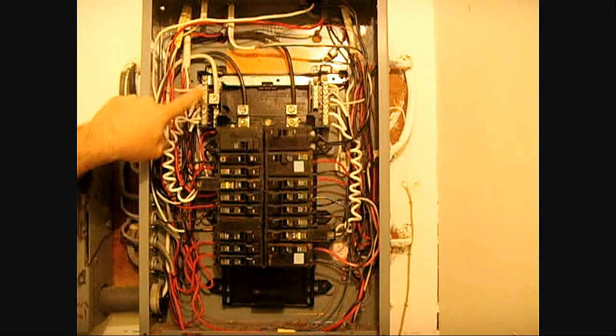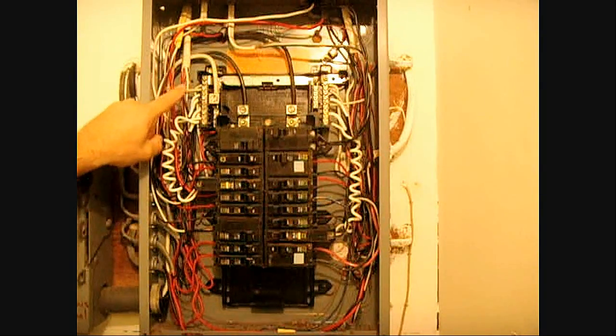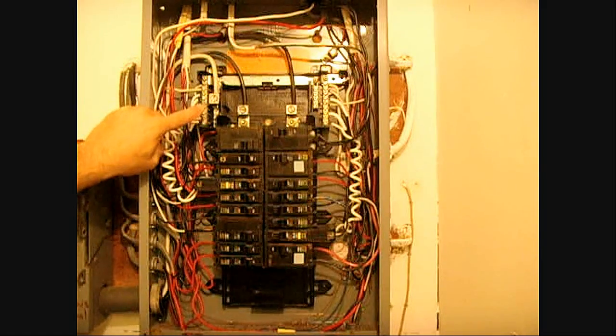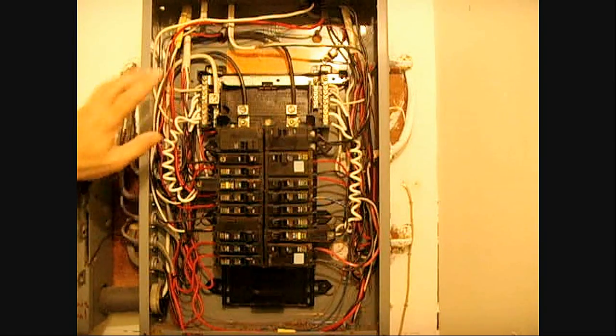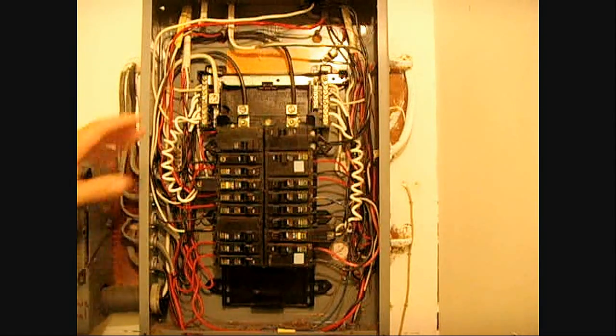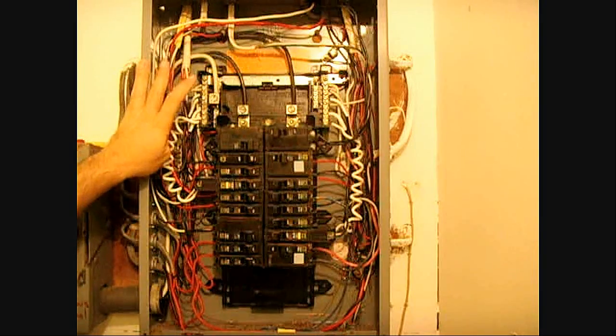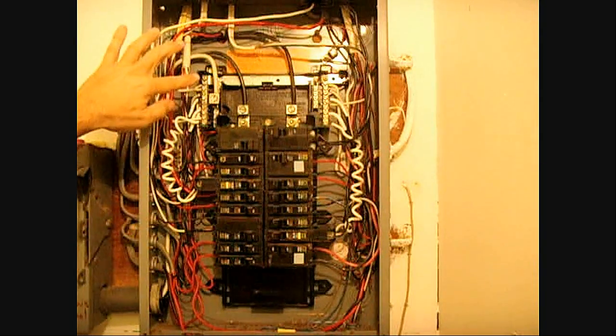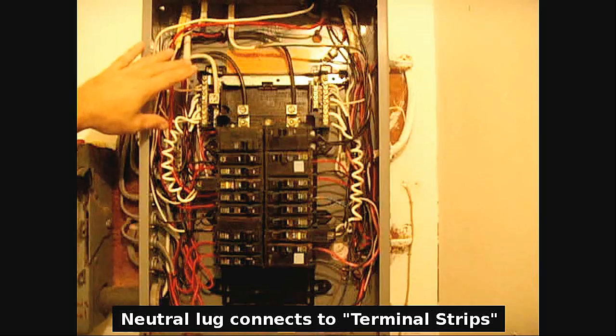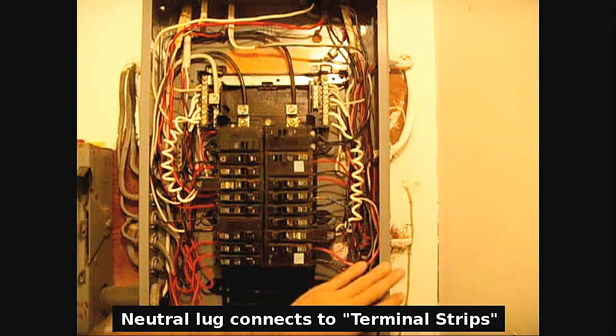And then you might see that the neutral or the white wire, these are always white or gray, may be a 1-aught copper. There's nothing wrong with that. So if you see one that's a little smaller for the neutral, you're fine with that. Now there's two ways the neutral is connected in the panel. Either it's isolated like you see here, or it's connected to the enclosure.